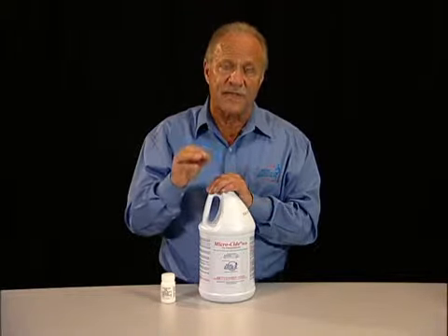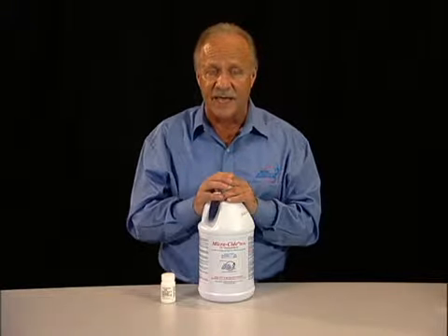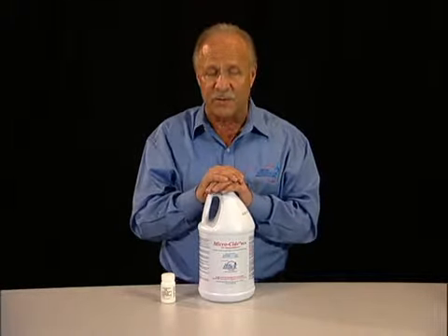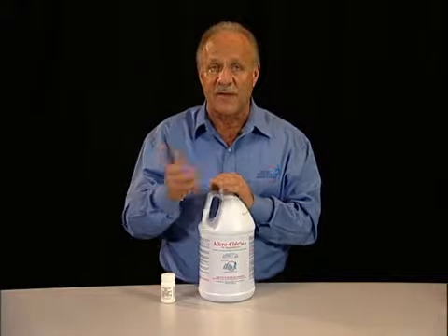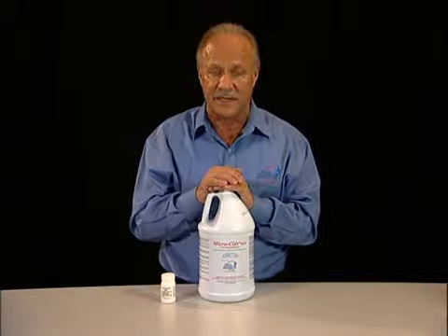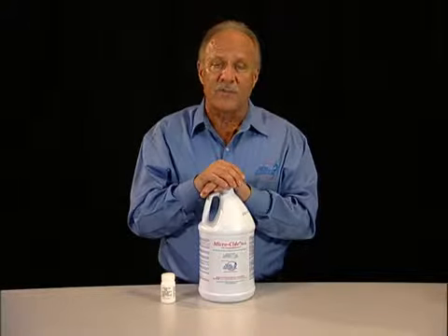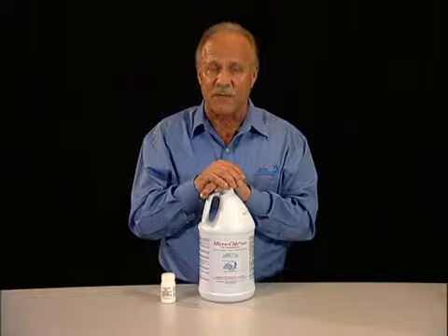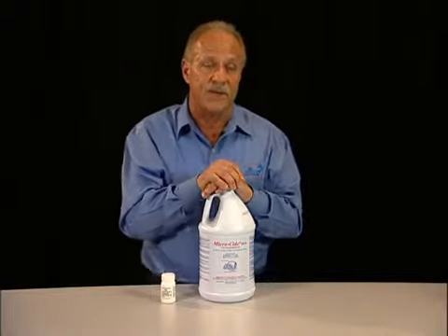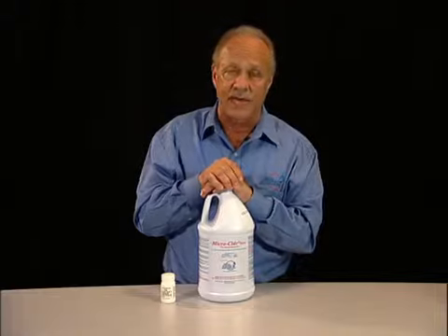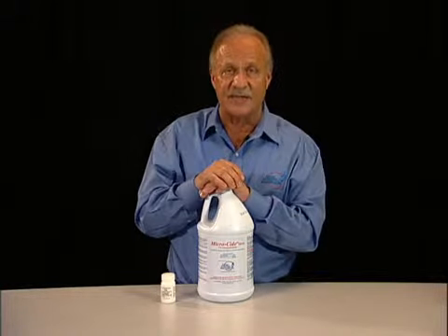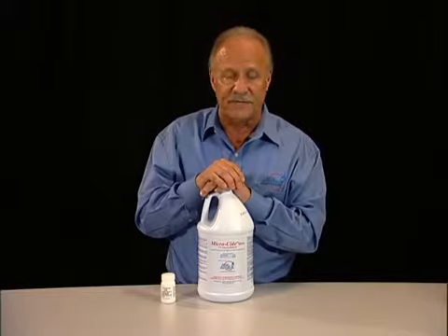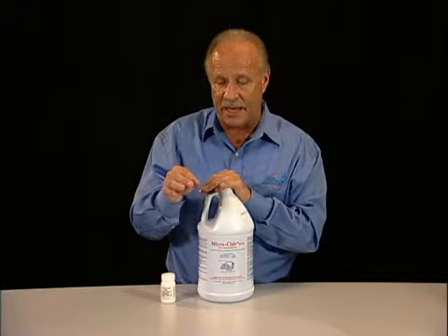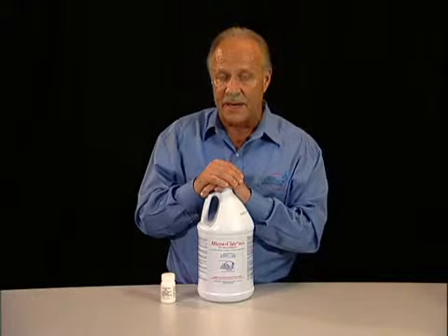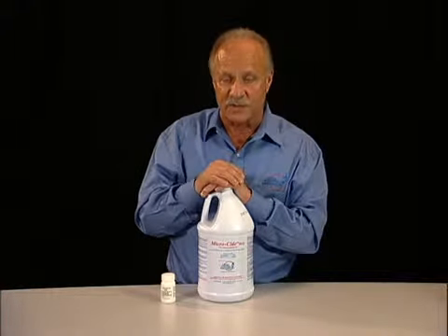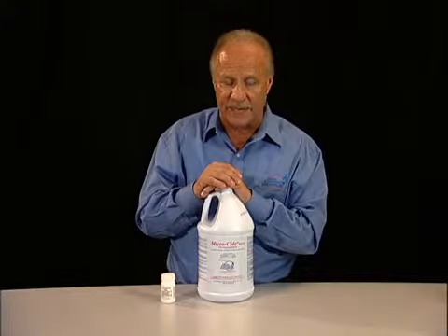The 28-day or 30-day product that Johnson & Johnson provides, and they have a little bit different formulation between the two, allows you to use the product for up to 28 or 30 days as long as you test it on a continuous basis. The other product that's presently sold is the Metrex product called Micro-Cide. They too make a Microcide 14 and a Microcide 28, which does the same thing as the Cidex product. It is a 14-day product requiring the daily monitoring by using a strip, and the 28-day by using a different strip to make sure that it's working for 28 days.